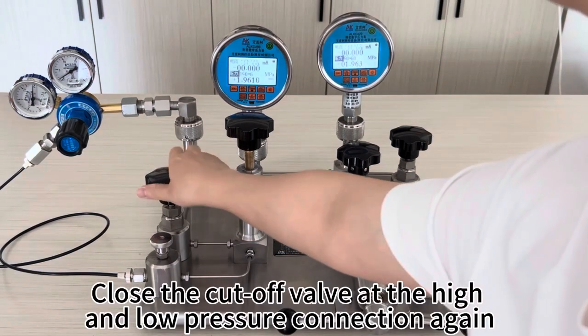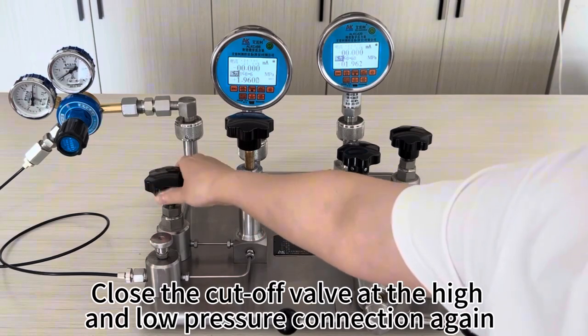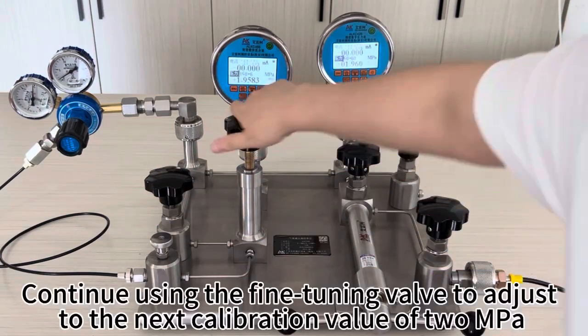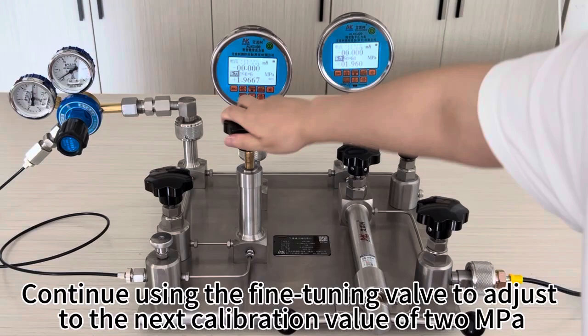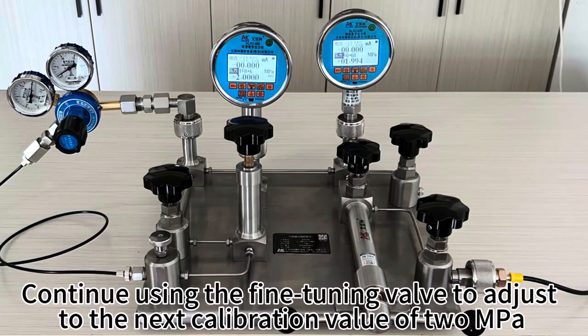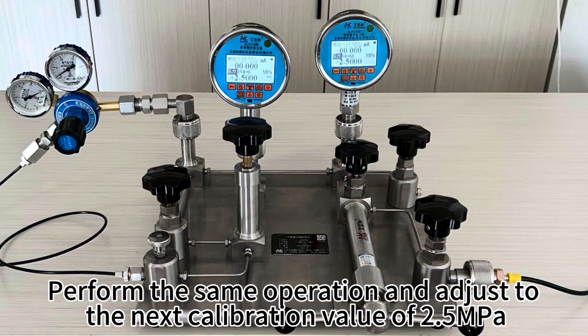Close the cut-off valve at the high and low pressure connection again. Continue using the fine-tuning valve to adjust to the next calibration value of 2 MPa. Perform the same operation and adjust to the next calibration value of 2.5 MPa.